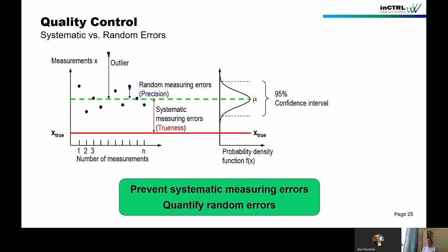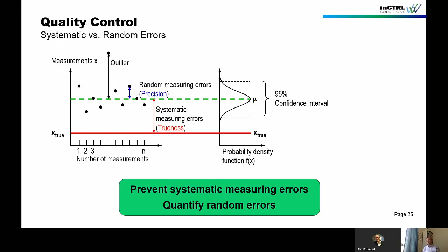That's also very important to set up your maintenance plan, because what you want is to trigger recalibration if there are systematic measuring errors. What you really clearly don't want to do is trigger recalibration based on random errors. You follow the random error, and that is just asking for trouble.